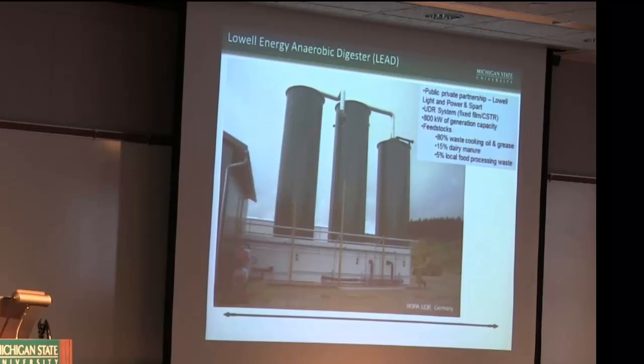By doing that, they allow these microbial communities to adhere and attach and stay inside of that digester. And by running dilute material through there, they can get a very high and very quick destruction of that organic waste. When you look at a complete mixed digester, which is probably the most common, if you put a gallon in today, it's going to stay there for 20 to 40 days. In a fixed film system like this, if I put a gallon of material in, it's probably coming out in the next 24 to 48 hours. So now we can drastically shrink the footprint. It's best used for materials that are really 98% water, though.